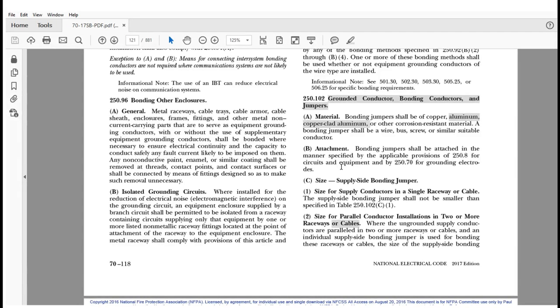So in the 2014 NEC, to size the grounded conductor, the main bonding jumper or system bonding jumpers or supply side bonding jumpers for an AC system, you would use 250.102 and of course table 250.102C1. That's where you would go. All right, but there again was no mention of grounded conductor sizing except in the table title. So they just added it to the actual 250.102 language, and so that's really the key part there. We all knew that you used it based on the table's heading and the direction, because that's really what you had to use, because that's what 250.102 guided you to.